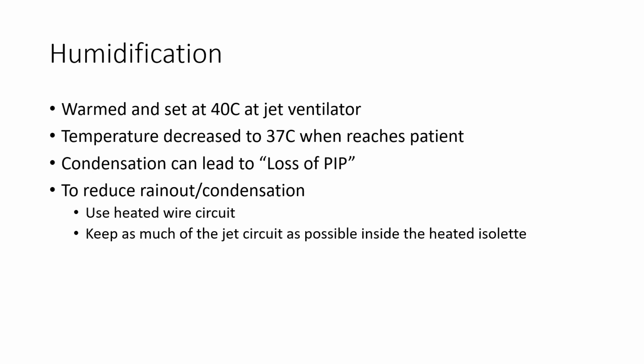The humidification temperature is set at 40 degrees Celsius. Since the gas is heated and humidified at the ventilator, it will cool as it travels through the circuit to the patient to about 37 degrees Celsius. Circuit rainout or excessive condensation can lead to a loss of PIP alarm and can be minimized by using a heated wire circuit and keeping as much of the jet circuit as possible inside the patient isolette. The respiratory therapist can remove condensation from the tube by disconnecting the green nozzle from the LifePort adapter and lifting the circuit towards the patient box and expelling the water through the circuit into a towel.